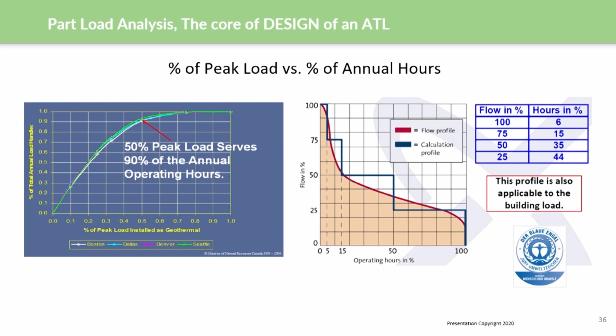If we look at part loading on these systems, incremental assets become extremely important. We can take a 100-ton incremental asset, like 100 tons from Karl's sewer system, and if we trickle charge it into the main loop 24 hours a day, we put back 2,400 ton-hours into that system. We can use water, or wastewater, in small amounts and actually make use of it because we draw on it for 24 hours.